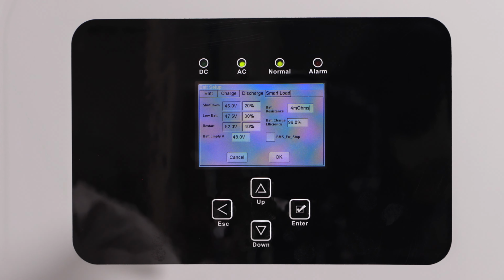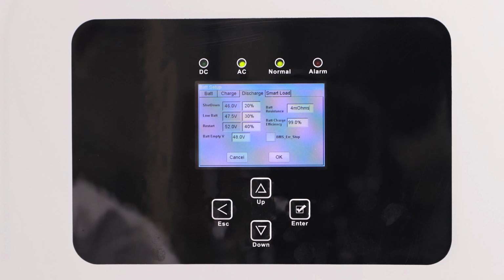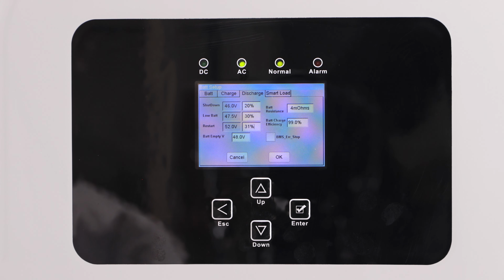Change the start percentage to 21%, but all the other settings should auto-populate, so go ahead and move to the Discharge tab. Set the shutdown to 20%, low battery to 30%, and restart to 31%.